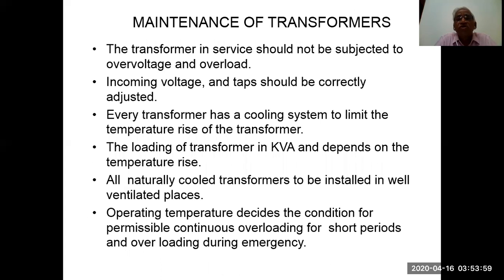Maintenance of transformers. The transformer in service should not be subjected to over voltage and over currents. Incoming voltage and taps should be correctly adjusted. Every transformer has a cooling system to limit the temperature rise of the transformer. The loading of the transformer in kVA depends on the temperature rise. Naturally cooled transformers to be installed in well ventilated places. Operating temperature decides the condition for the permissible continuous overload for short periods and overloading during emergency.